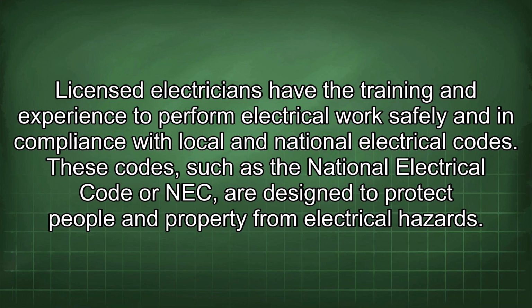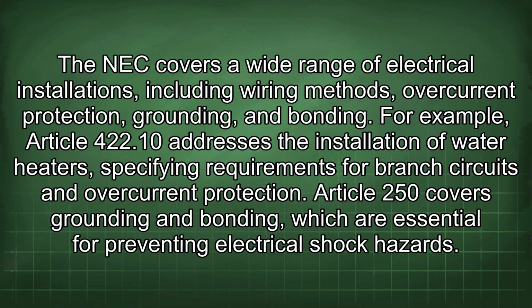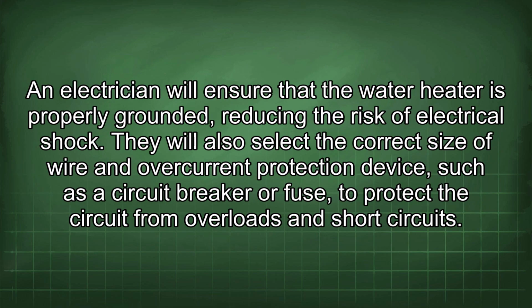codes. These codes, such as the National Electrical Code or NEC, are designed to protect people and property from electrical hazards. The NEC covers a wide range of electrical installations, including wiring methods, overcurrent protection, grounding, and bonding. For example, Article 422.10 addresses the installation of water heaters, specifying requirements for branch circuits and overcurrent protection. Article 250 covers grounding and bonding, which are essential for preventing electrical shock hazards. An electrician will ensure that the water heater is properly grounded, reducing the risk of electrical shock.